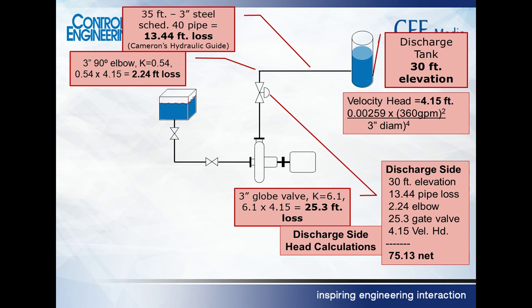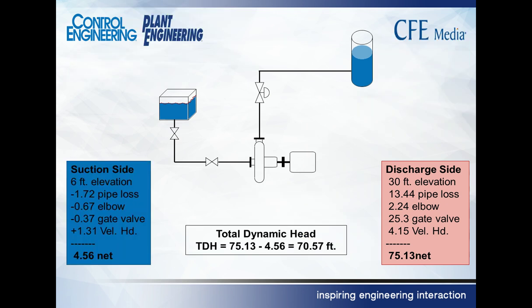Let's add those all up. What do we get? 75 feet of head on the discharge side. I've got 4.5 feet coming in as a positive, and 75 on the other side. What's the difference between the two? The total dynamic head at 360 gallons per minute is about 70.5, 70.6 feet of head.